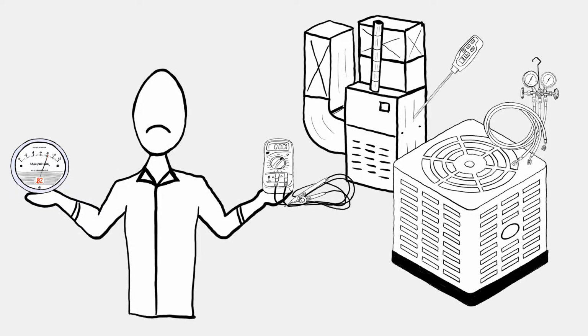Unless the system has proper fan airflow, you can't know for sure if the amp draw, refrigerant pressures, or temperature differentials are even correct.